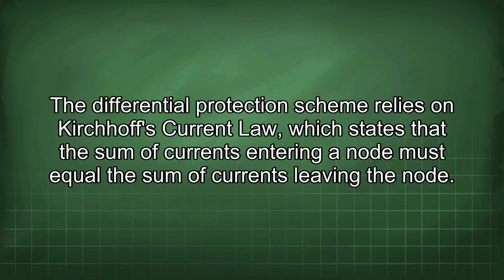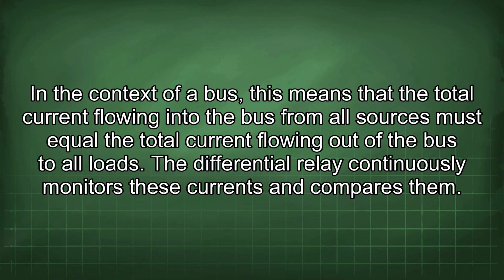The differential protection scheme relies on Kirchhoff's current law, which states that the sum of currents entering a node must equal the sum of currents leaving the node. In the context of a bus, this means that the total current flowing into the bus from all sources must equal the total current flowing out of the bus to all loads. The differential relay continuously monitors these currents and compares them.